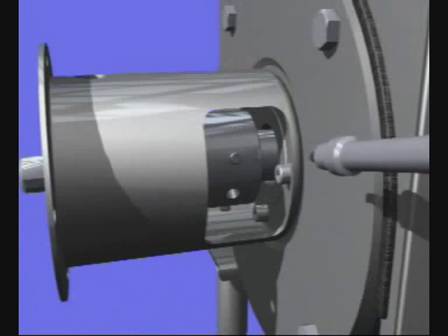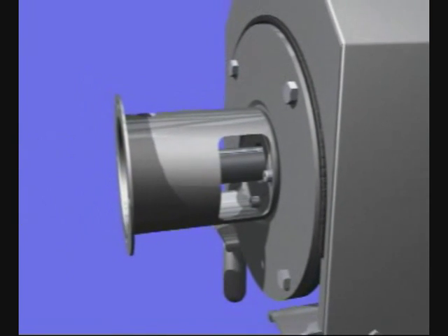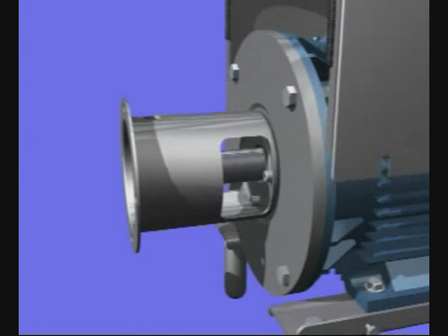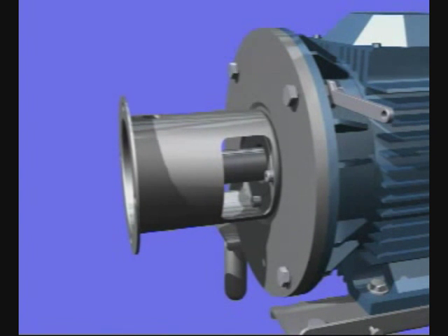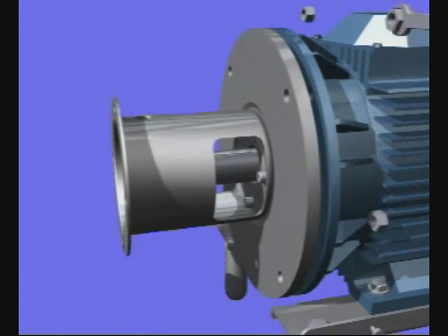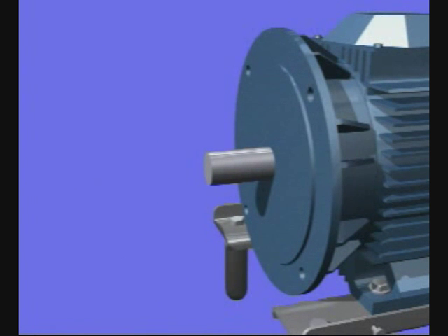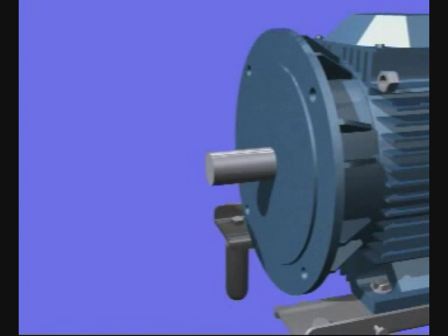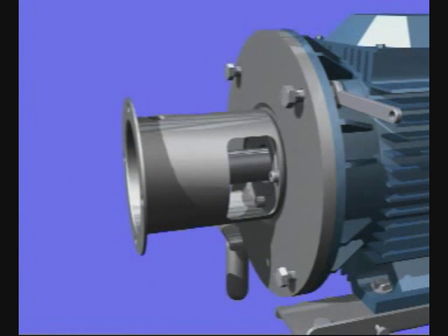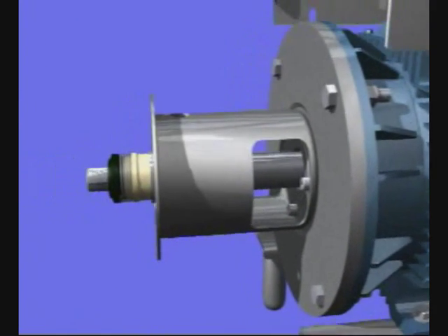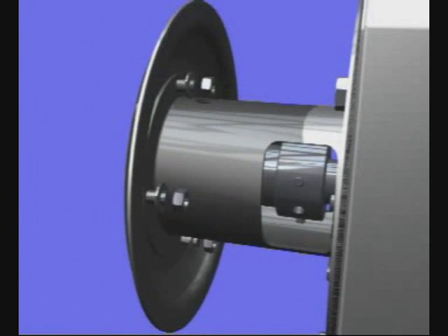Loosen the pin screws in the coupling and remove the shaft and coupling. Remove the shroud. Loosen the bolts in the flange. Remove the adapter. You can now access the motor for servicing. Reassemble the adapter. Fit the shaft and coupling without tightening the pin screws. Fit the back plate, washers, and nuts.